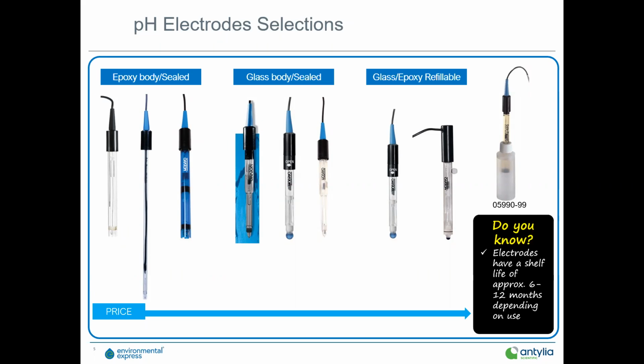So your sealed electrodes are obviously the lower cost electrodes. The epoxy body, polycarbonate bodies are very durable, great for use out in the field. They normally have a shelf life of 6 to 12 months, depending on usage, depending on the application that they're seeing. Now, refillable, obviously, we have customers that have the refillable electrodes used that'll last 2, 3, 4, 5 years in lifespan before the reference finally gets attacked and is no longer stable.